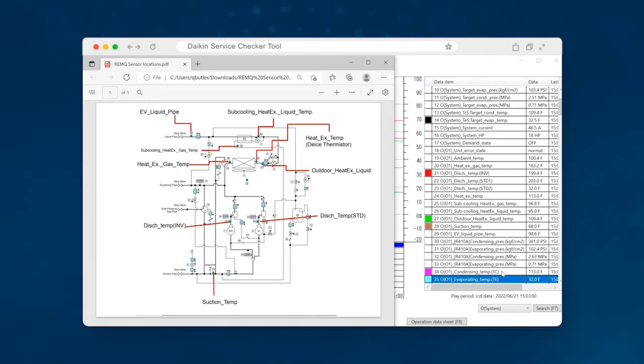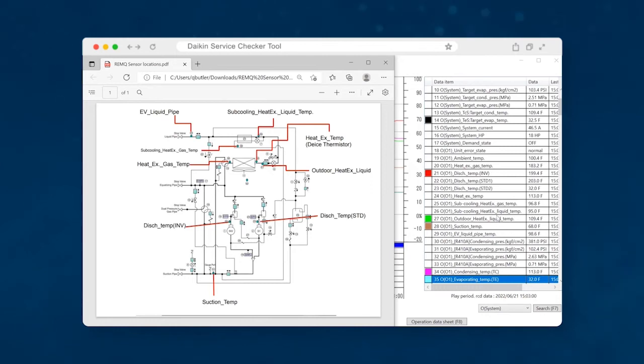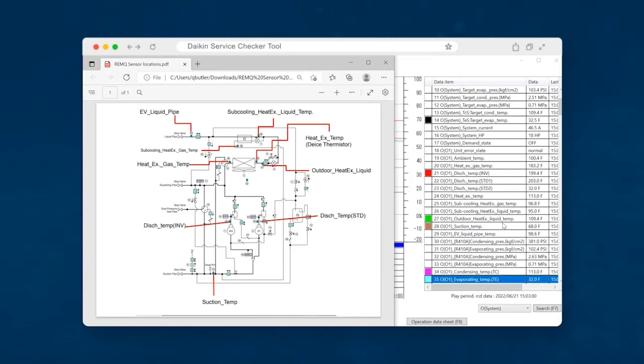But there's one more item that's worthy of checking, and that's going to be the outdoor heat exchanger liquid temp and your condensing temp. That's how we measure subcooling. Once again, this is the basic method of measuring subcooling for any conventional system. So we take our condensing temp and we subtract our liquid pipe temp. And so in this instance, that's going to give us four degrees. So the range for that for VRV is supposed to be between eight and fourteen degrees. So once again, we don't have enough subcooling. So once again, that's another indication of shortage of refrigerant charge.